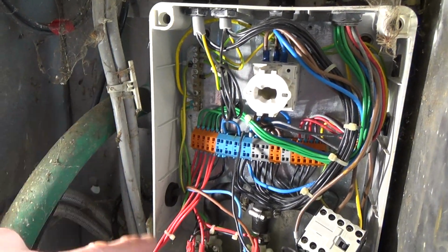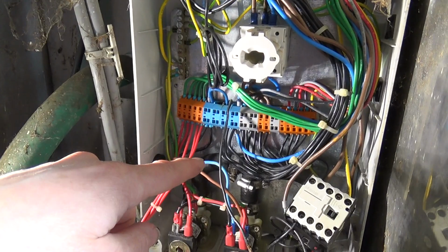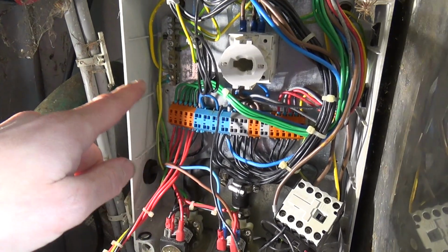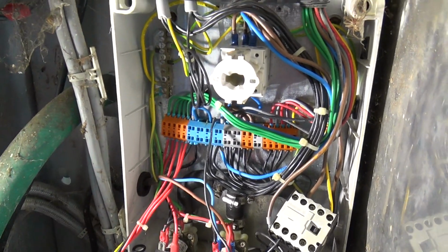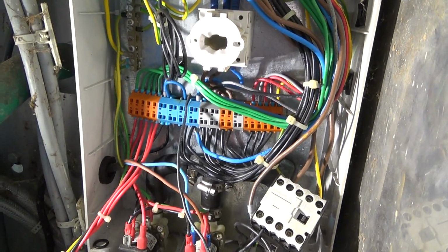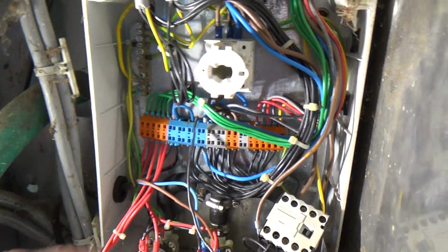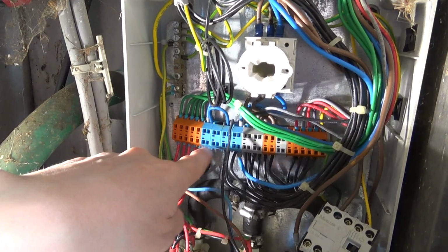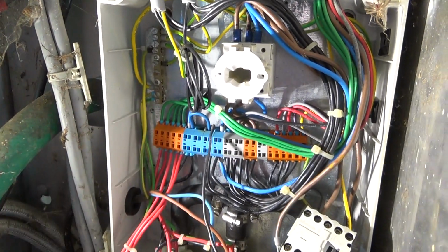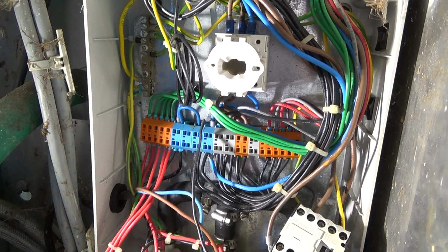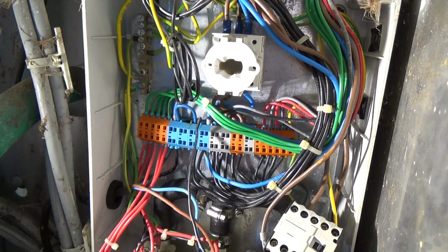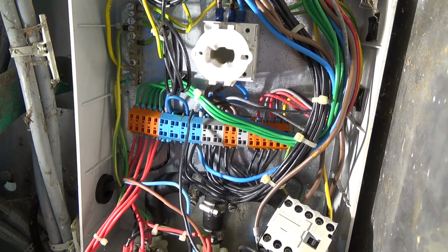If they didn't, the neutral could be floating. You could have 50 volts to earth on the neutral and then 300 volts to earth off the others, I suppose. So anyway, yeah. That might be a legacy of this burnout here. Somebody might have just done a few swapping overs and put things where they shouldn't be.